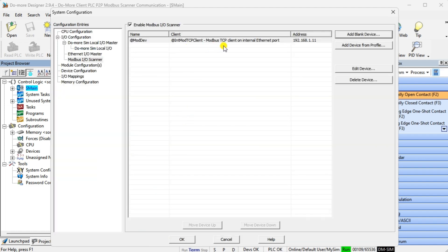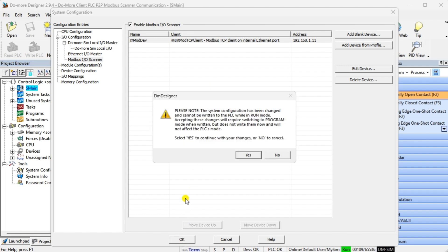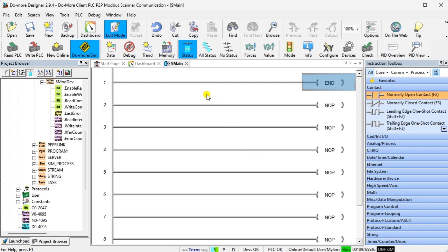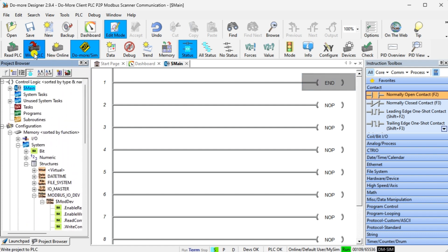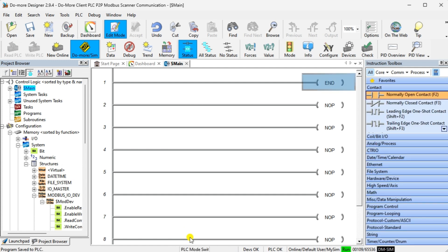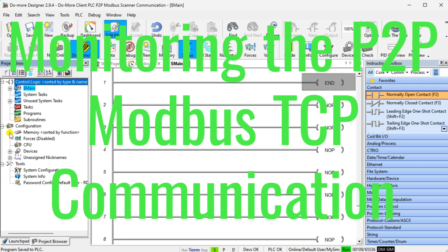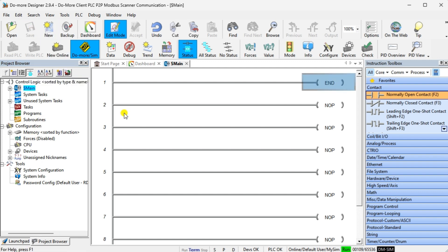Once we have all the data, select OK. A warning message will be displayed indicating that system configuration has changed. Select OK and download the program to the Client PLC Simulator. Monitoring the P2P Modbus TCP communication — ensure that both the PLC and Simulator are running. We can now monitor the P2P Modbus TCP communication by monitoring the scanner. Call the Modbus Scanner Monitor by selecting it from the main menu, Debug.